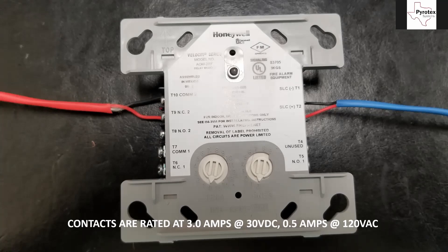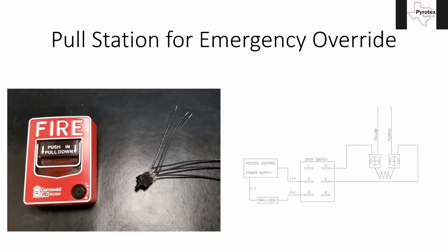The last point is using pull stations for the emergency override switch. Here's a Gamewell pull station — this is actually a conventional pull station, not the addressable one. Beside it, there's a second switch that has six wires coming off the back: three going up one direction and three bent down going another, forming two different sides to this switch, each with a separate circuit.